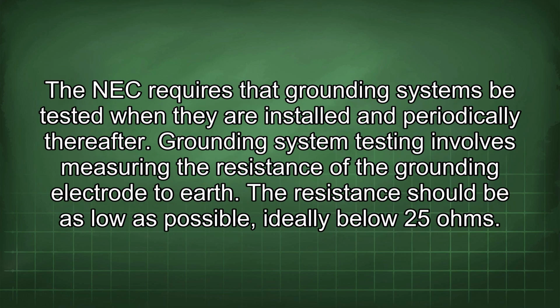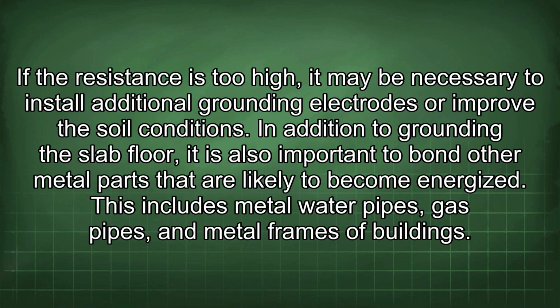The NEC requires that grounding systems be tested when they are installed and periodically thereafter. Grounding system testing involves measuring the resistance of the grounding electrode to earth. The resistance should be as low as possible, ideally below 25 ohms. If the resistance is too high, it may be necessary to install additional grounding electrodes or improve the soil conditions.